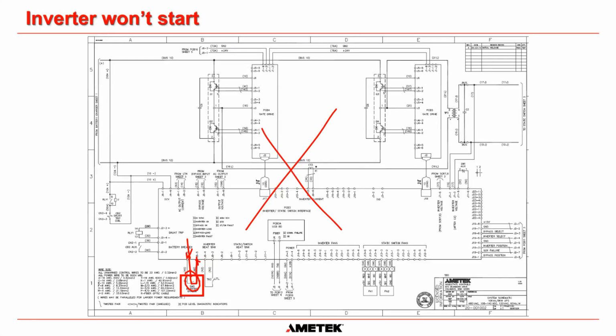So if the inverter is not switching on and you have greater than 105 volts DC, the next thing you should check is to make sure that inverter enable switch is closing when you switch it to the on position. And you can either measure at the board itself or on the terminals of the switch itself. You can even switch the system off completely and measure with a Fluke on resistance across these terminals. It should be open when the switch is off, and it should be closed when the switch is on.